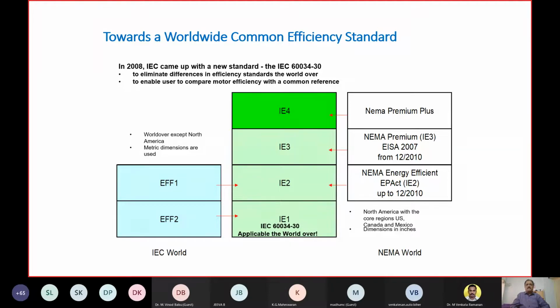Now that gave rise to IEC 60034-30 in 2008, where globally a harmonious standard was required, and therefore IEC and NEMA agreed upon a new international efficiency standard as IE1, IE2, IE3, IE4 and so on. Today we are discussing IE5, not yet adopted, but a few manufacturers like pump manufacturers have come with IE5. But with the induction motors, the growth in efficiency is from IE1 to IE2 to IE3 to IE4 presently. One or two slides I will try and cover the higher efficiencies, the limitations of induction motor technology and so on.